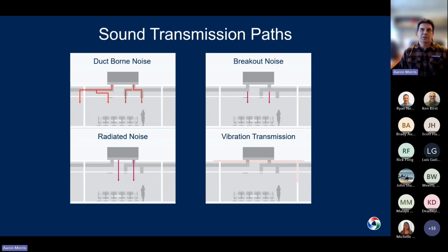Radiated noise that's coming directly from the equipment, radiating out in all directions. So depending, again, if this is a rooftop piece of equipment, like you see in this example, you're worried about the noise radiating down into the space. If it's a mechanical room, you might be concerned about it radiating through the walls, that sort of thing. And then finally, vibration transmission, where the vibration from the equipment could potentially be transmitted through the structural components of the building and causing noise or vibration complaints in the space.